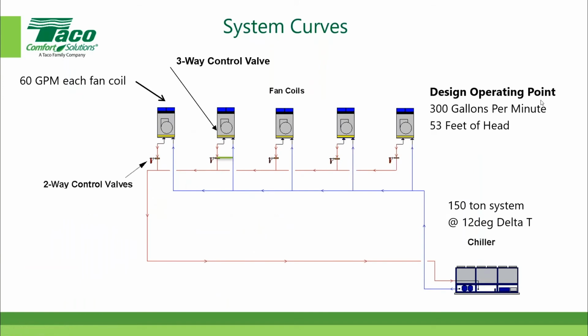Okay, the first thing we want to talk about is, let's say we have this oversimplified system here. Somebody has figured out that it's a 150-ton system. They did some calculations, and they also selected a 12-degree delta T, and it's a chilled water system. Ours is very, very simple.